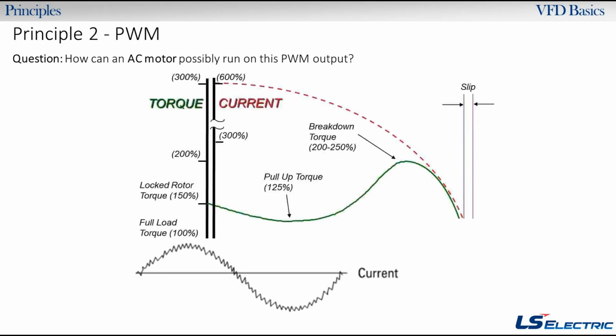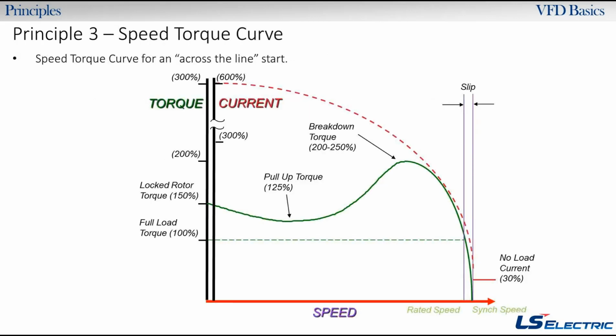All right, so what is the advantage of all of this? Why do we want to adjust the motor speed and the motor torque versus just running across the line? Well, there's a few different reasons. A lot of times your process doesn't need to run 100% speed, especially if we get into the fan and pump world. Rarely do applications need to run at 100% capacity. So if you just reduce the speed slightly, you're going to be saving a lot of power and a lot of energy.